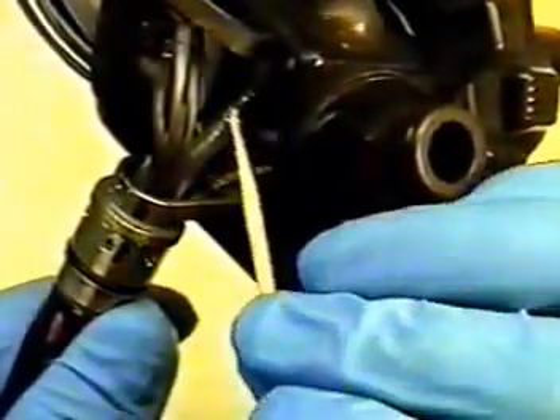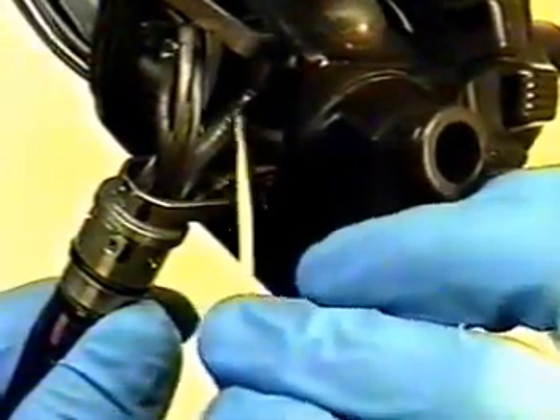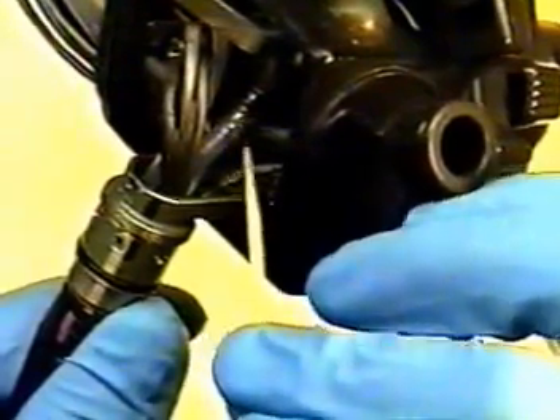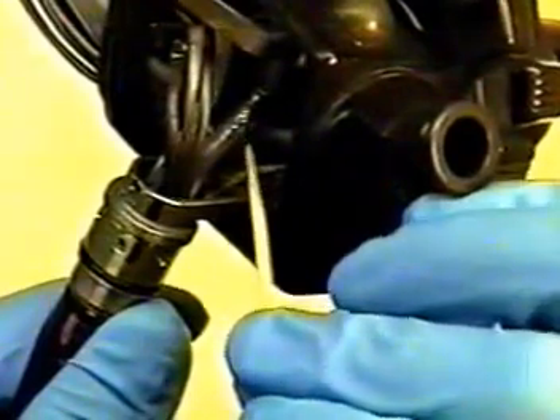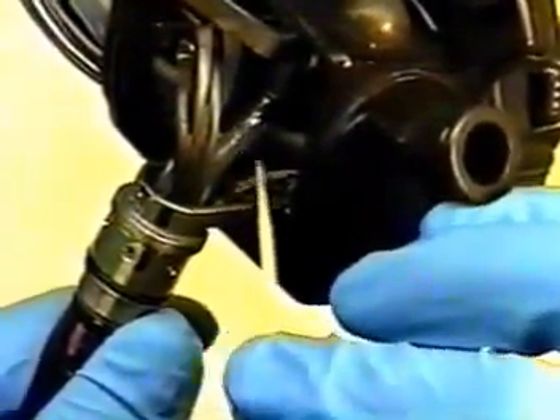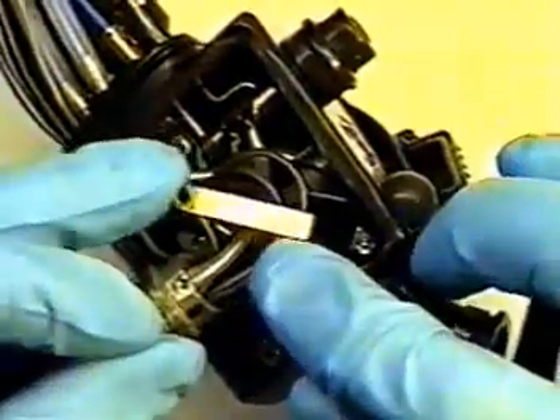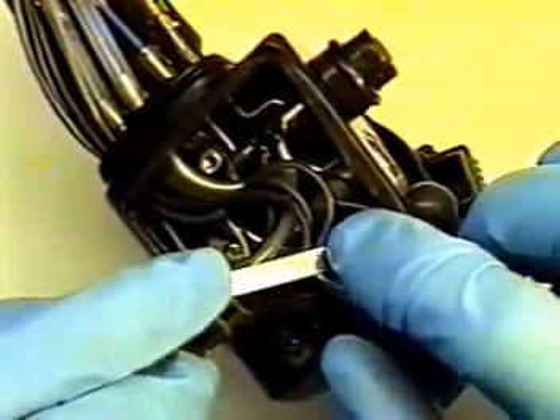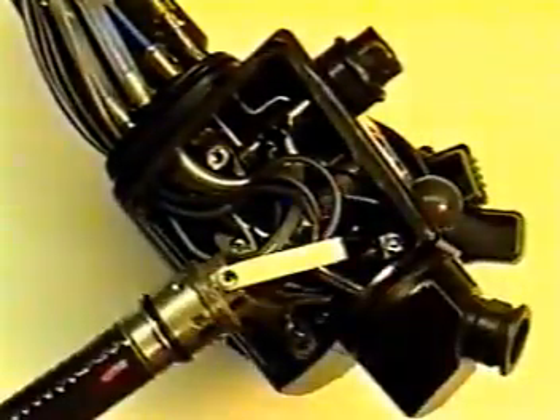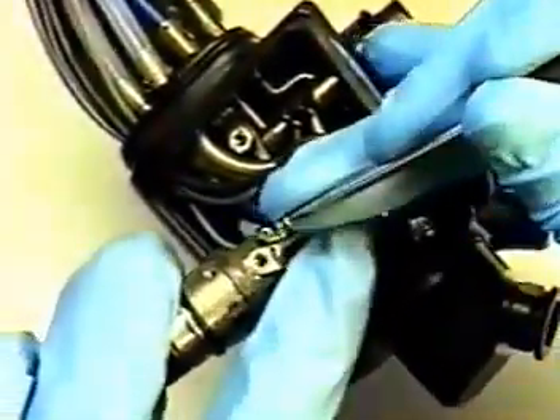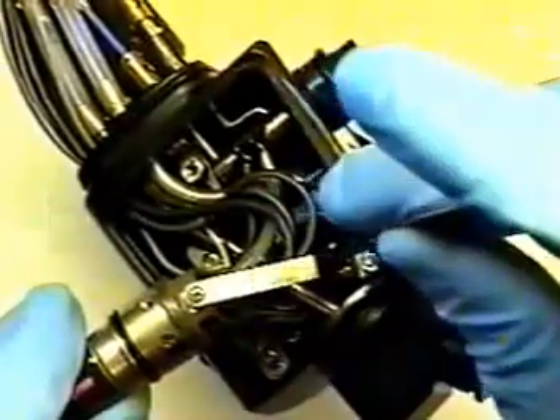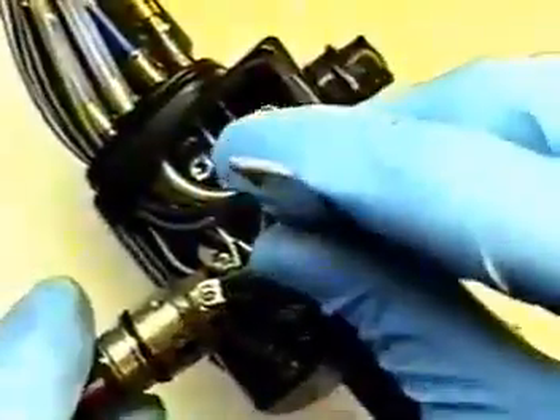Once the tube is over the port, use the remaining glue and cover the top of the suction channel so that we are sure we have an airtight seal and the suction channel will not pull off. Once the glue is dried on the suction channel port to the suction cylinder, we can carefully swing over our retaining bracket. Be careful not to pinch our light guides or CCD wire harness or air water channels. Slide over, retrieving the flathead stainless steel screw and tightening down the bar. Also take your pair of tweezers and tighten the screw and locking shaft.